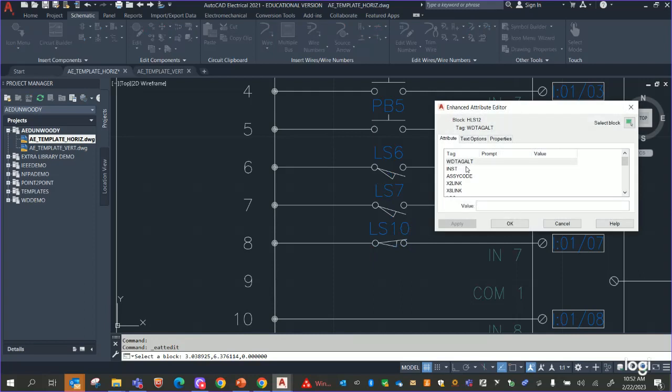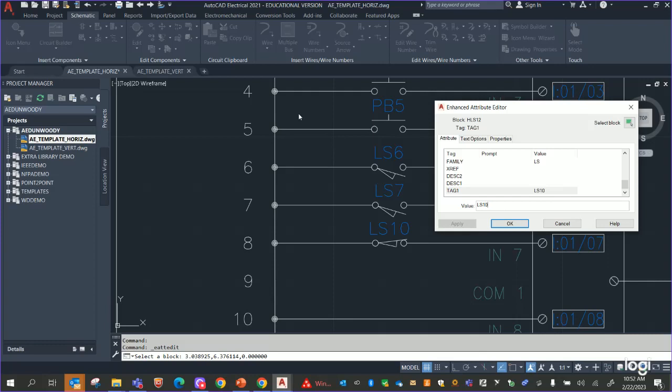As an example — if I just place a normally closed limit switch without going to lookup, when you open it you're not going to get a manufacturer or catalog number. Nothing. But if you go to limit switches, pick normally closed, and go to lookup, I can pick that same exact limit switch and select that I want to use the normally closed contact on it. Now I've got the catalog data. It asks again if I want to map it — I prefer not to. I'll also update this tag to make sure it lines up appropriately.